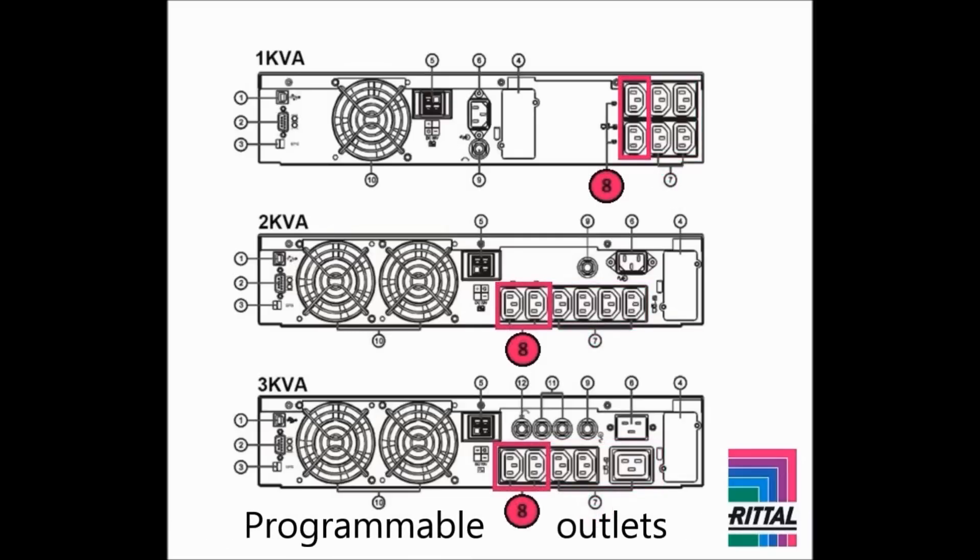The programmable outlets can be configured using the free software. The programmable outlets can be used for connection of uncritical loads. These outlets can be configured to automatically switch off when certain conditions have been met. This could prolong the autonomy time for critical loads during a mains power failure.